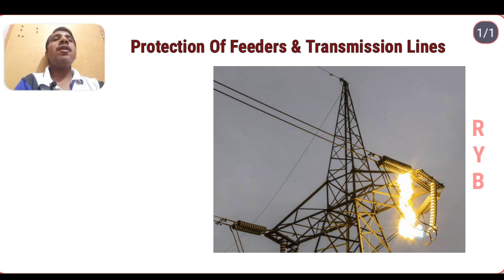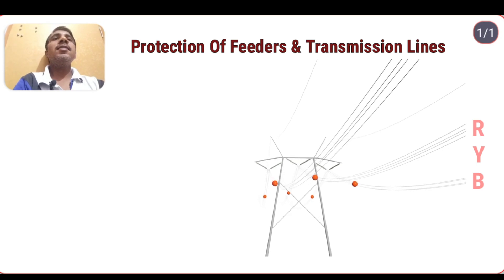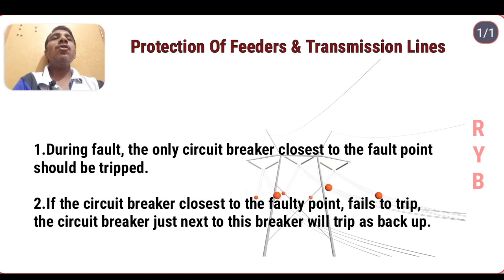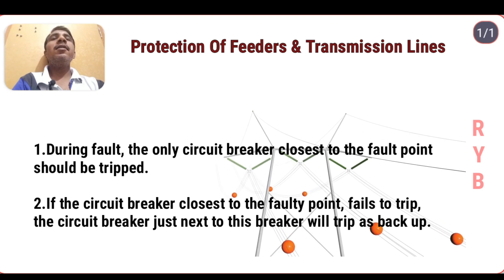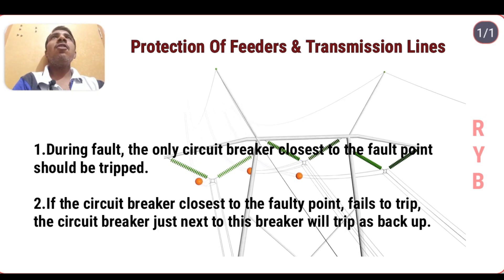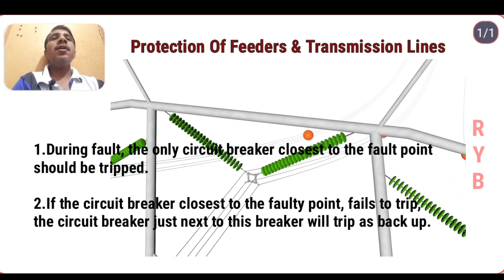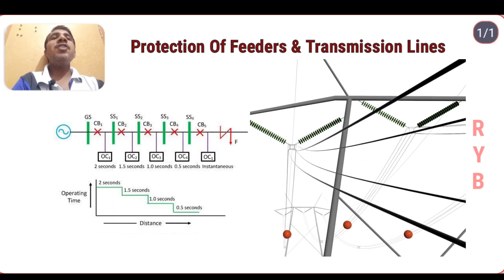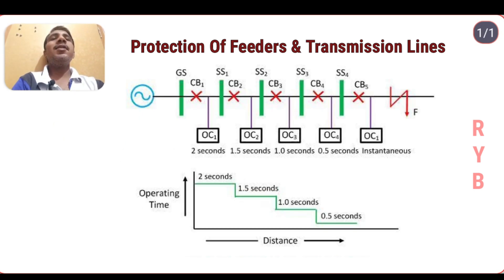Protection of lines should have some special features. During a fault, only the circuit breaker closest to the fault point should be tripped. If a far-away circuit breaker trips instead of the nearest one, different lines will be subjected to unnecessary interruptions. If the circuit breaker closest to the fault point fails to trip, the circuit breaker just next to it will trip as backup protection.